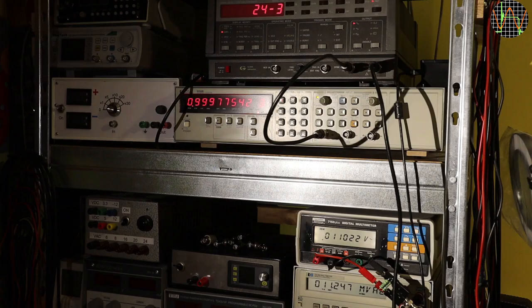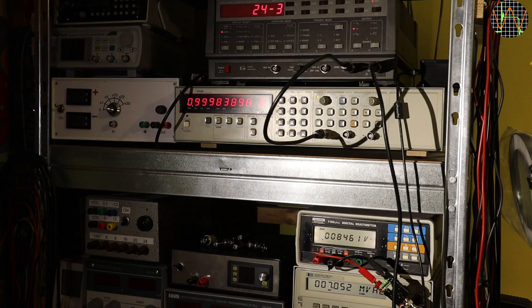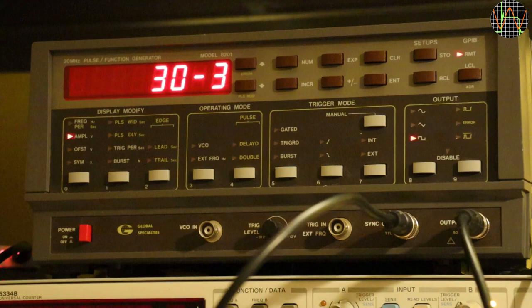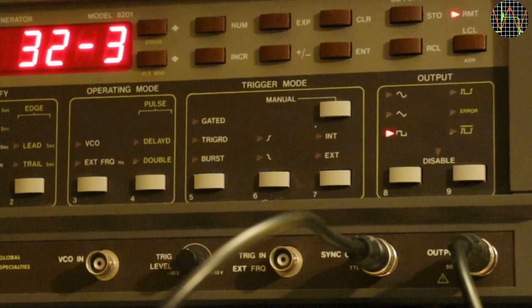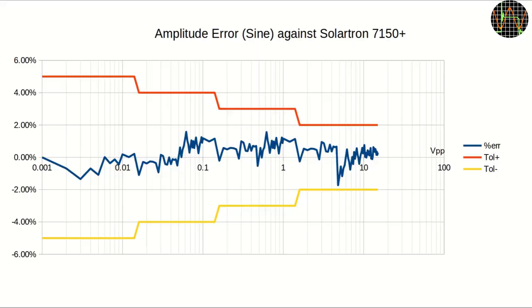Anyway, I decided to run a test ramping up the amplitude from 1mV to 15V in about 170 steps and measure the result. There is something fascinating driving this machine remotely with all its discrete indicators instead of a display screen as in modern generators. As you can see in this test, I actually cycled through all the waveforms for each step. Here is the result for sine waves, the other waveforms look very similar. I used the logarithmic X axis otherwise the millivolts would all be bunched up on the left. The red and yellow bars are the tolerance values from the spec. As you can see the generator meets its specification but to be honest, ±2% as the tightest tolerance is pretty generous.